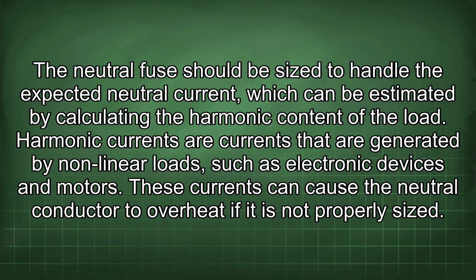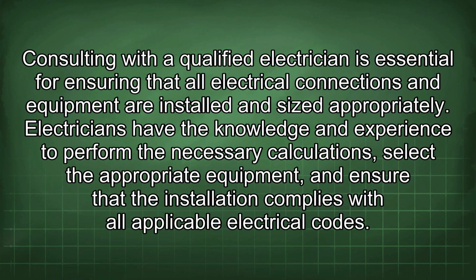The neutral fuse should be sized to handle the expected neutral current, which can be estimated by calculating the harmonic content of the load. Harmonic currents are currents that are generated by nonlinear loads, such as electronic devices and motors. These currents can cause the neutral conductor to overheat if it is not properly sized. Consulting with a qualified electrician is essential for ensuring that all electrical connections and equipment are installed and sized appropriately. Electricians have the knowledge and experience to perform the necessary calculations, select the appropriate equipment, and ensure that the installation complies with all applicable electrical codes.